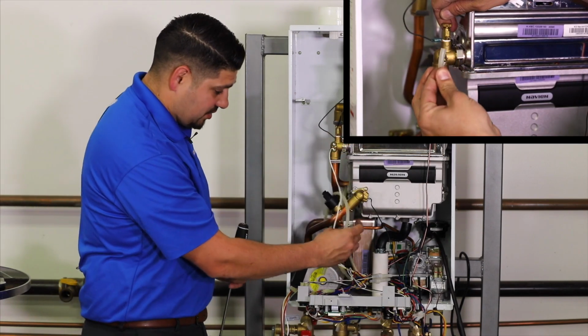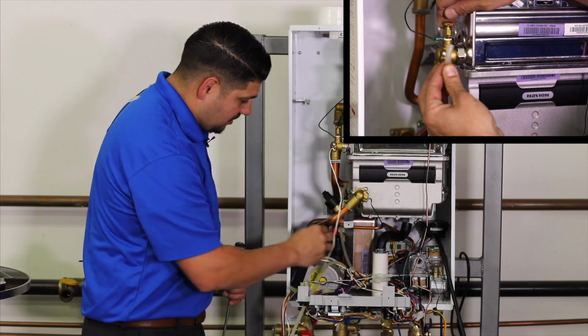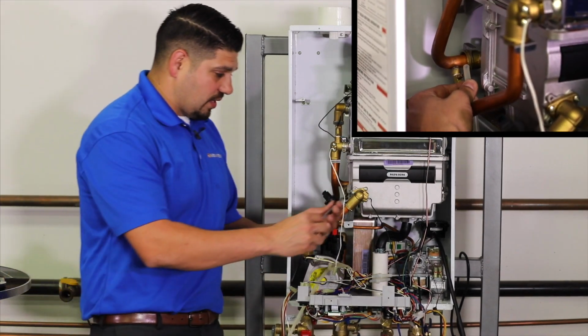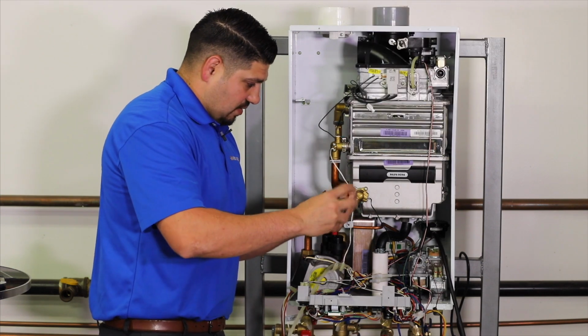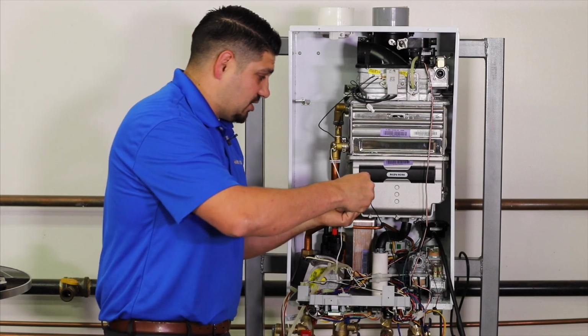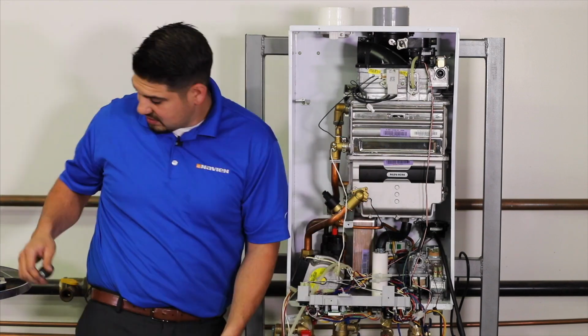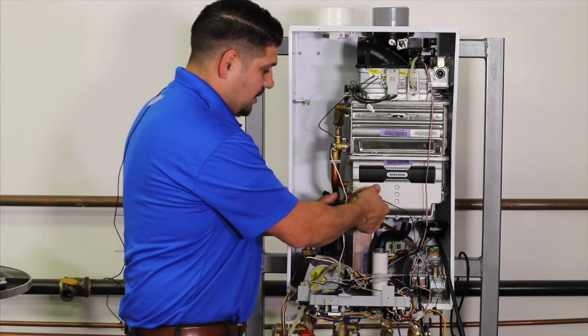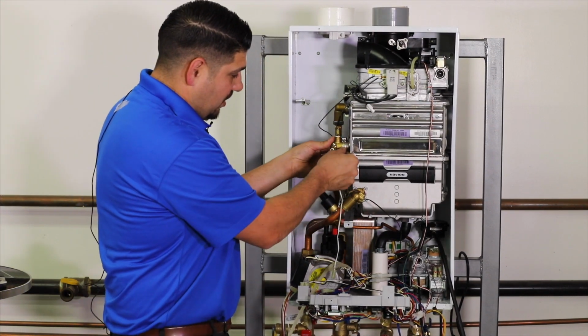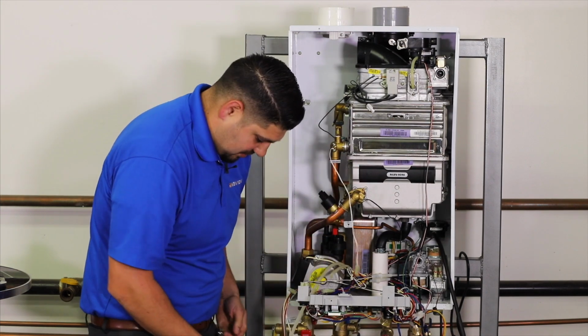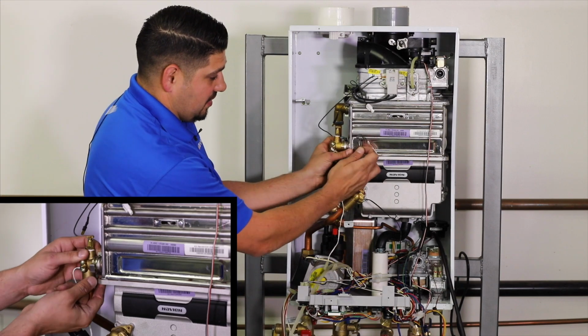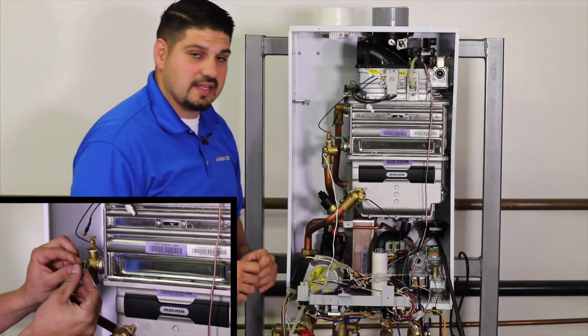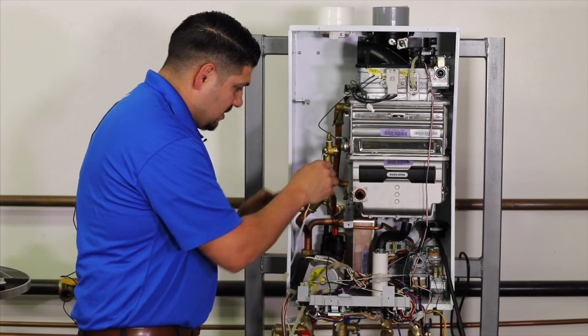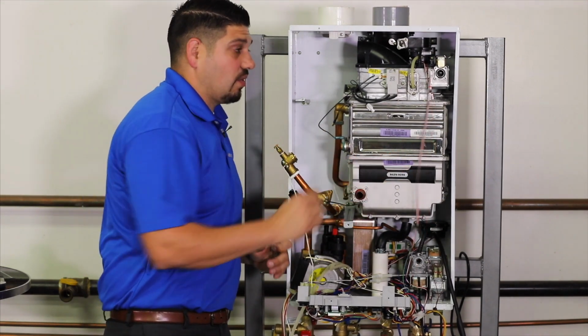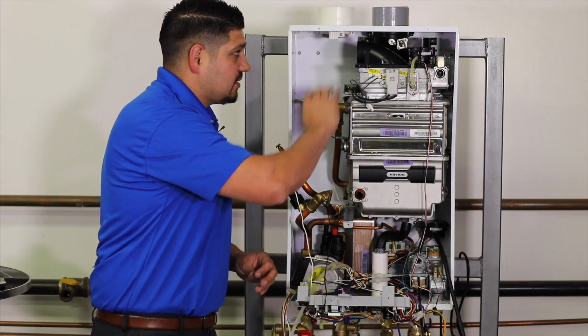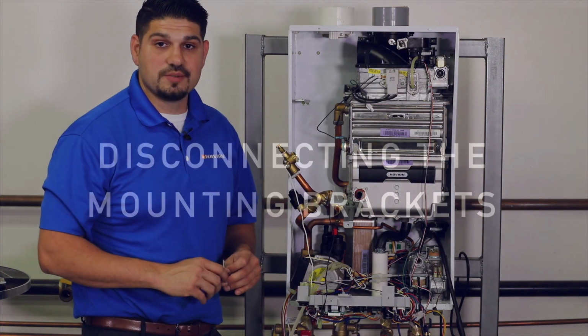These hoses, just pull them right off. Shouldn't take too much. That's one. There's one in the back here. I'm going to disconnect that, and then we're going to unscrew our brass elbows from the heat exchanger itself. Set these screws aside, and you can just pull it right off. And on the primary, or your upper heat exchanger, these clips, well, caught it, pop right off, and then pull that right off. So now the plumbing is disconnected. You can move this aside, and now we're able to start taking off the mounting brackets and some of the ductwork, and we're able to remove this heat exchanger.